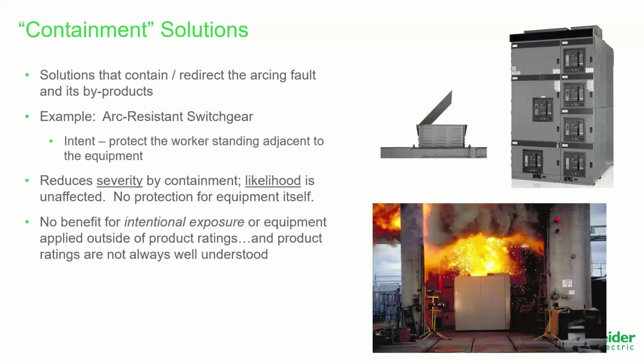Unfortunately, though, no protection for the equipment itself. Also, I'll say no benefit for intentional exposures. What do I mean by that? One example would be when you're doing voltage testing to verify that the equipment is dead during part of a lockout tagout procedure. Most of the time, that means opening a compartment or removing a cover in order to get access to do that testing. When you do that on arc resistant gear, it's not arc resistant anymore. And so, we may have to consider that, again, considering the tasks that you're looking at.